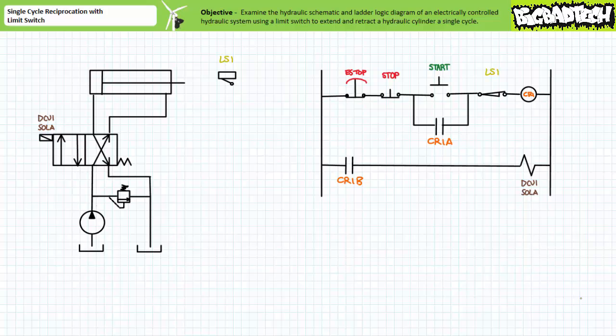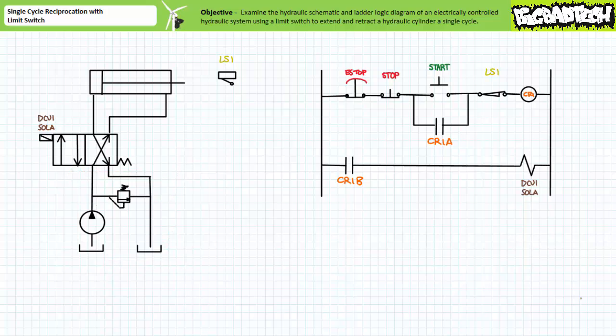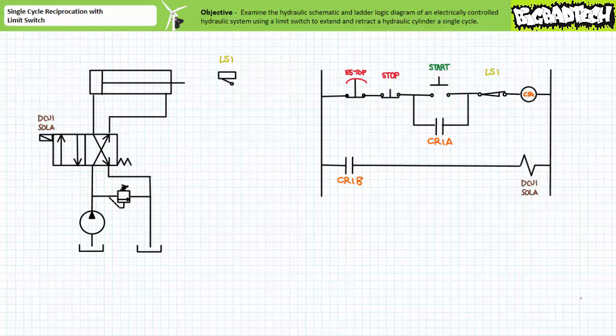Let's start with an examination of the hydraulic schematic. Here we've got a hydraulic power unit consisting of a pump, reservoir, and pressure relief valve combination. If at any time system pressure exceeds that of the setting of the normally closed pressure relief valve, the pressure relief valve will open and allow a relief passageway to the tank. Here is a directional control valve DCV1, used to stop, start, or change directional fluid flow on our hydraulic circuit. It is a two-position spring-offset solenoid-activated directional control valve. In its deactivated state it is spring-offset to the cross-connect position where pump flow is routed to B and tank to A.